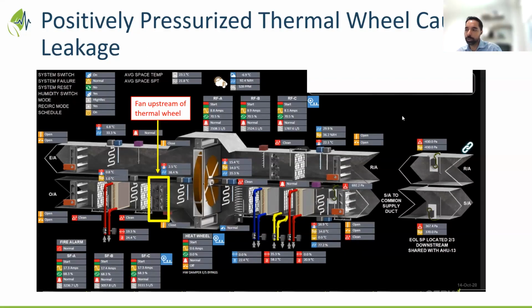Another thing is to ensure that your seals are sealed properly closed in this case, so you don't expect that cross contamination. But the key to this is to make sure the balance of the supply and exhaust flow is maintained, and your seals are properly aligned, so you don't get that cross contamination with these systems. And how would the hospital know, as you say, that the purge is going in the right direction, that it's going from supply to exhaust? How would you know that?